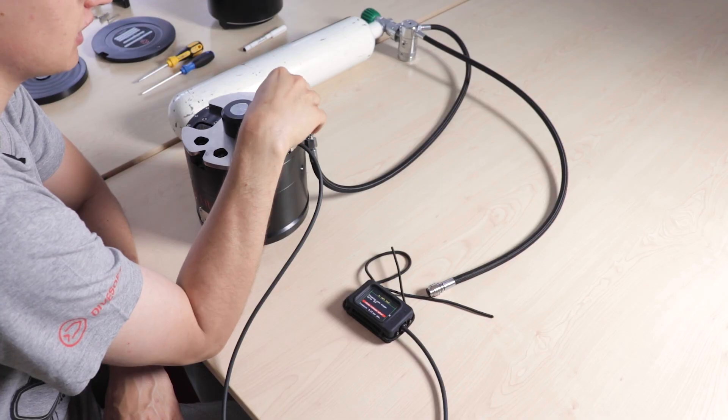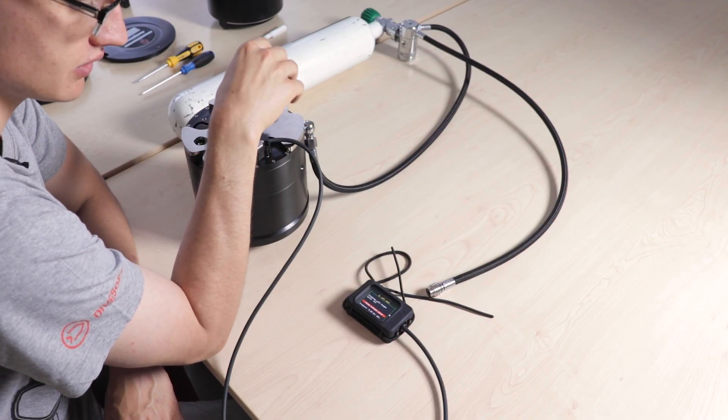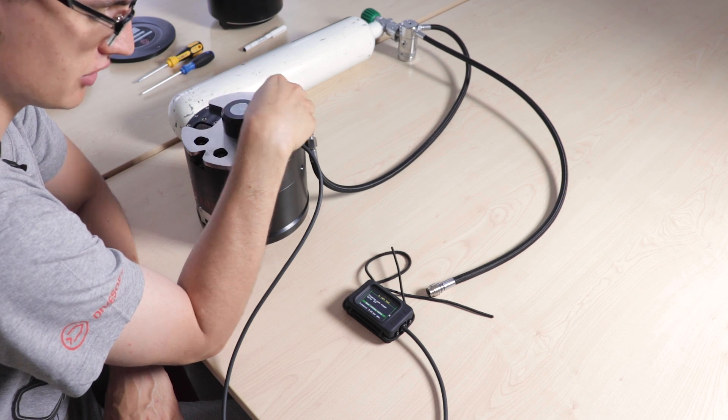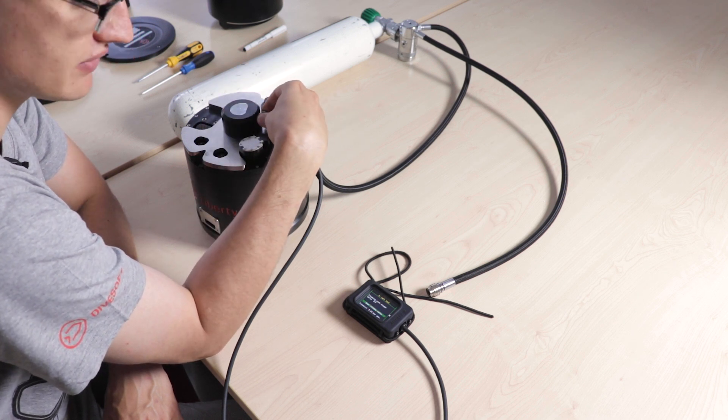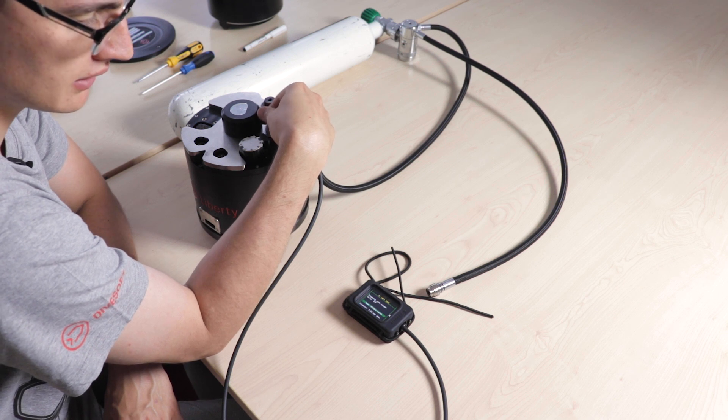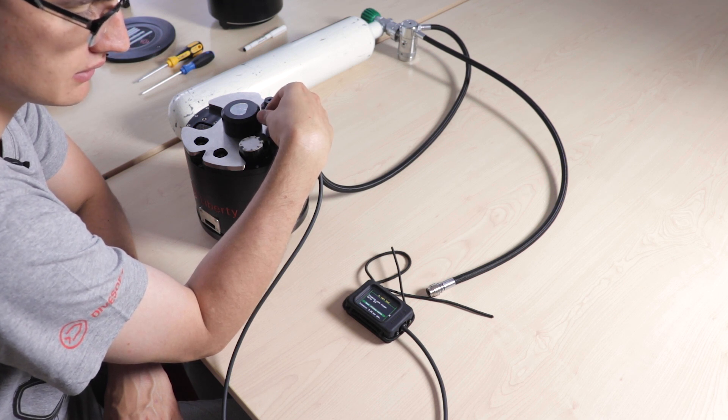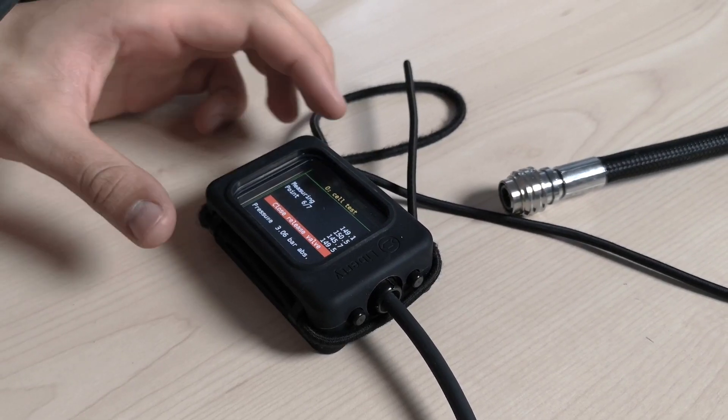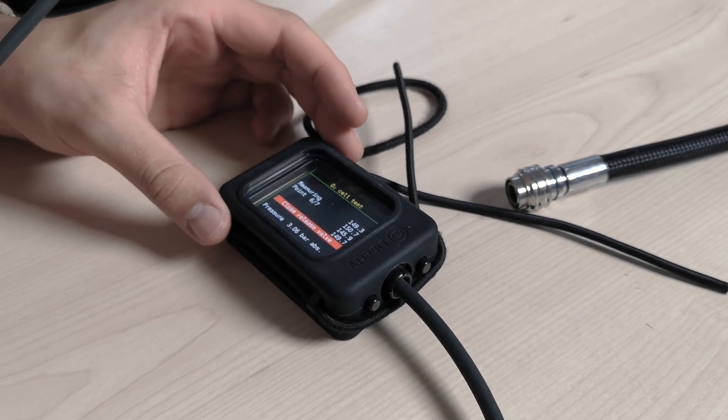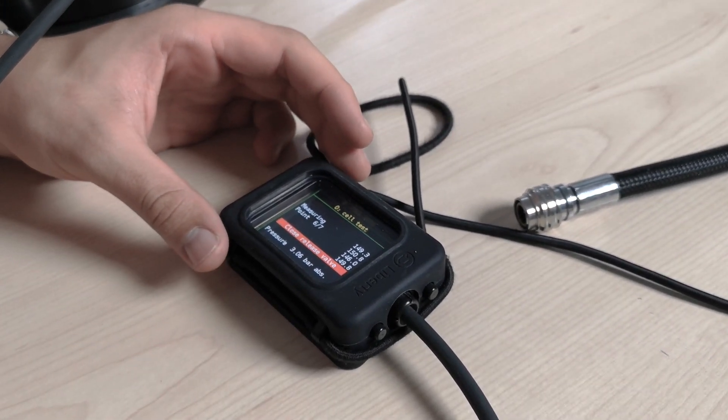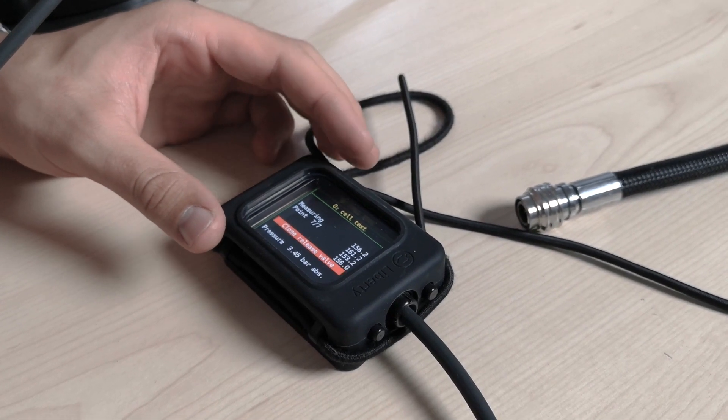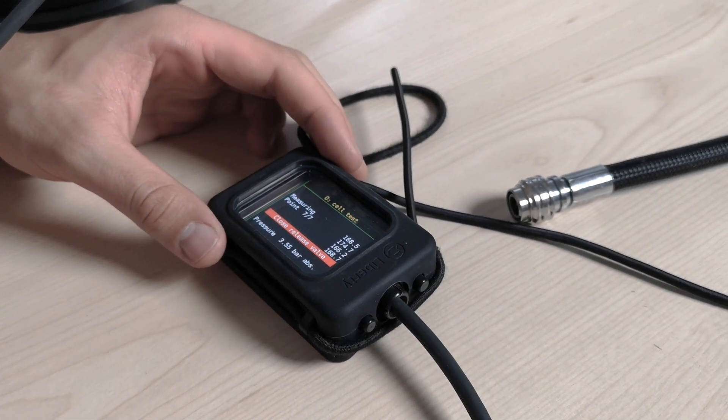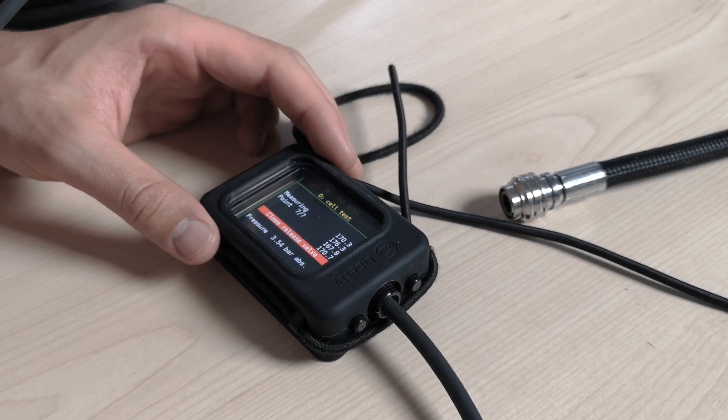Now it automatically cycles five times through high pressure. It tells you when to open and when to close the release valve, so just follow along and it'll be done in no time. Right now, it adds 0.5 bars every time and measures the potential on every single oxygen cell.